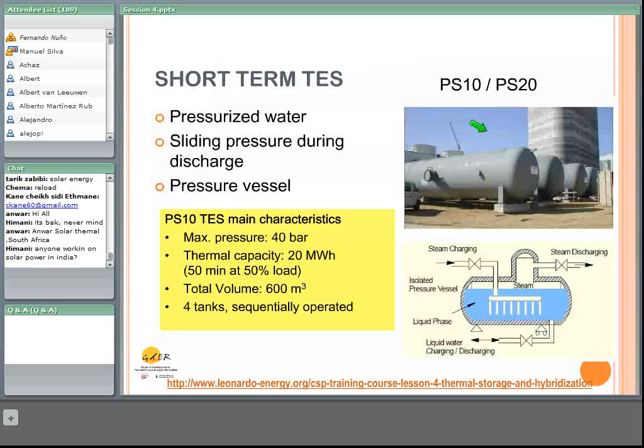In this picture, you can see the tanks of the thermal storage system of PS10. They use pressurized water, and there's a sliding pressure mechanism during discharge of the storage system. Of course, the vessels must be pressurized. They are pressure vessels, so they are rather expensive, and they cannot be very big. The main characteristics are described here.